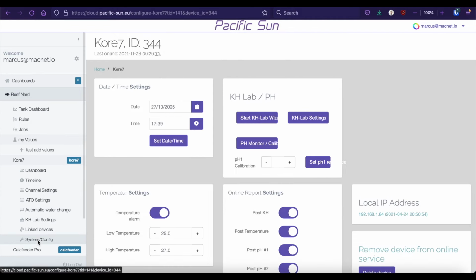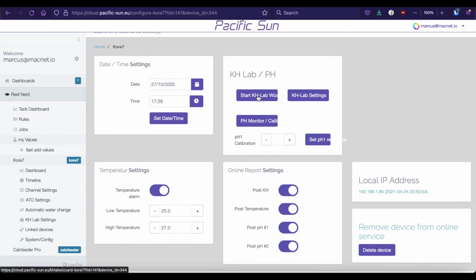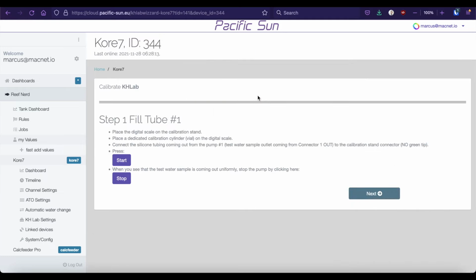Finally, the last area here is the system settings config area, and this is where you'll come in to do much of your setup. In here is the KHLab wizard. This is where you'll come to do your initial setup, and it's a step-by-step guide. It gives you instructions all the way along in terms of calibrating each of the first 3 pumps, and you just simply follow the instructions to go through and weigh how much is being dosed out of each pump, enter the values into this wizard screen, and continue through to the next step, and it'll walk you through the process of calibrating the salt water in, the reagent fluid in, and the wastewater out pumps to get yourself fully up and running.